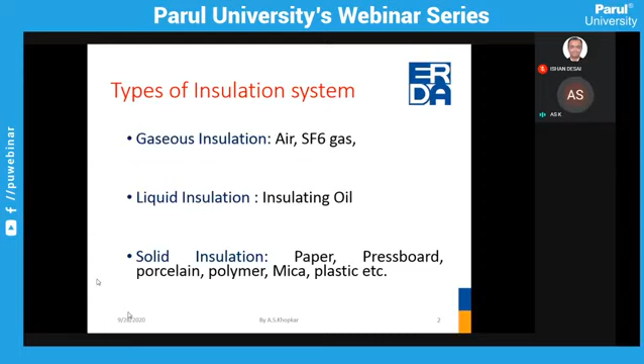This insulation system, basically, if we talk about high voltage, any insulation system is divided into two categories: self-restoring type insulation and non-self-restoring type insulation. Self-restoring type insulation means, if you study high voltage, disruptive discharge. Whenever we apply high voltage, or when the voltage exceeds the breakdown value of the particular object, a disruptive discharge will occur. If a disruptive discharge occurs in the insulating media, and after the disruptive discharge the insulating media regains its original property, then it is called self-restoring type insulation. On the other hand, if after disruptive discharge the insulating media loses its original dielectric property, then it is called non-self-restoring type insulating media.